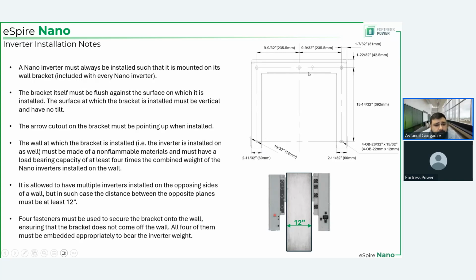Use 4 fasteners to secure them in place. 1, 2, 3, 4. And also, if you have a scenario where there are multiple inverters on opposite sides of the same wall or structure, that structure, as we said, must be able to support 4 times the combined weight of all the inverters that it's supporting, and the thickness of the wall, i.e., the horizontal distance between the two brackets, should be no less than 12 inches. Am I missing anything? Did I say everything? Yeah, I think I covered it all.